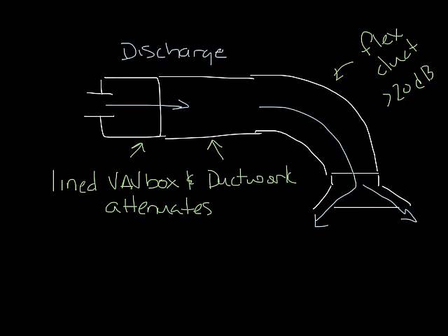For this reason, discharge sound of VAV boxes is not usually a big concern. We do see a lot of unlined duct work. If you have unlined duct work, you need to be careful about discharge sound. Externally lined duct work is not acoustically the same as internally lined duct work, because the sound doesn't see the liner, so it basically just bounces back and forth inside the duct work, and then escapes through the diffuser into the space.